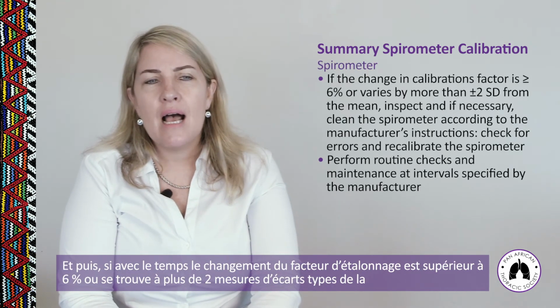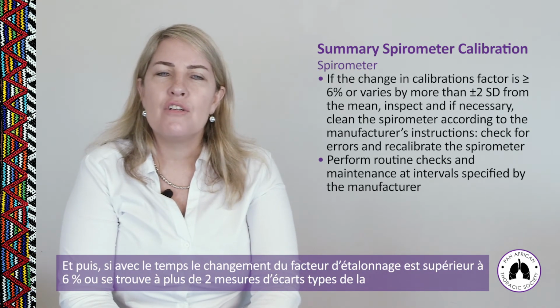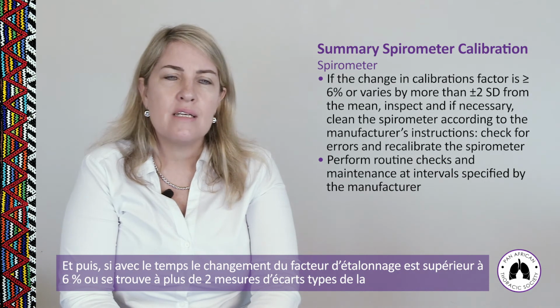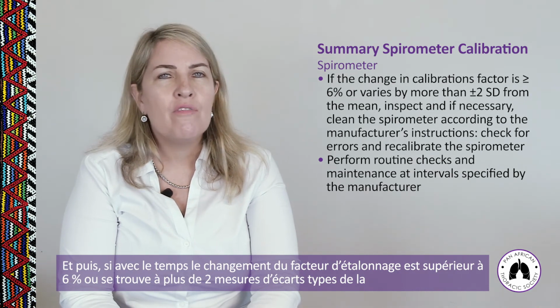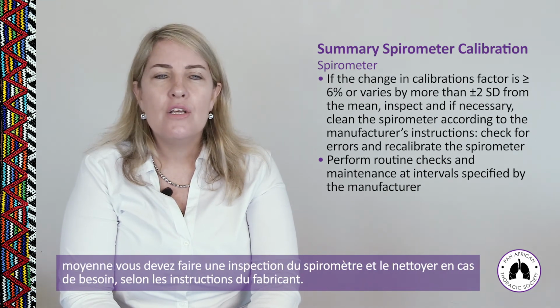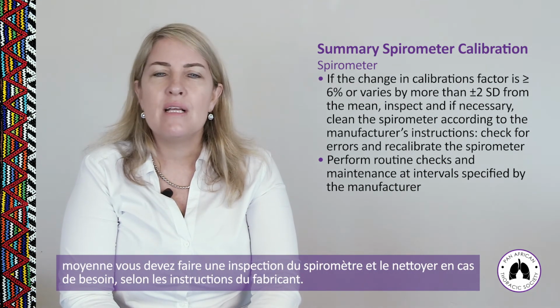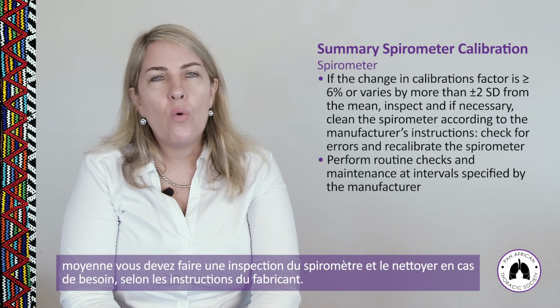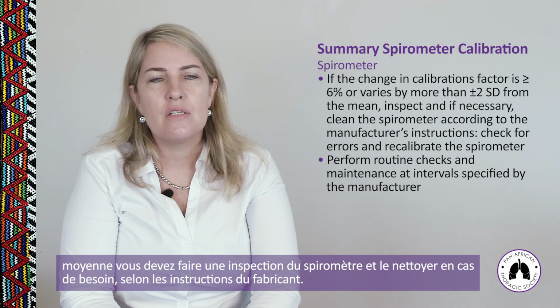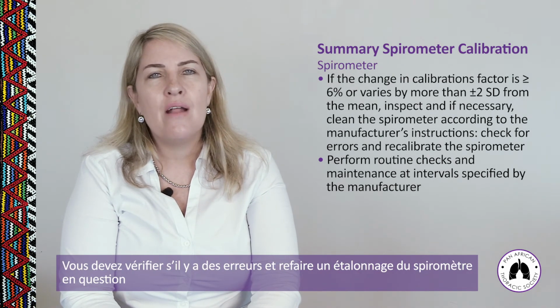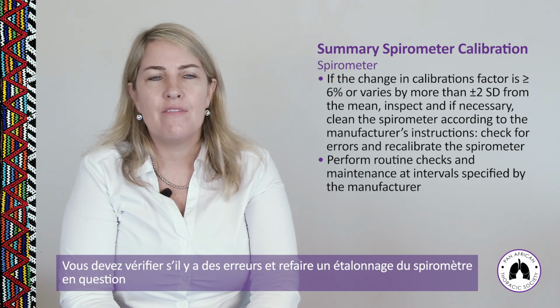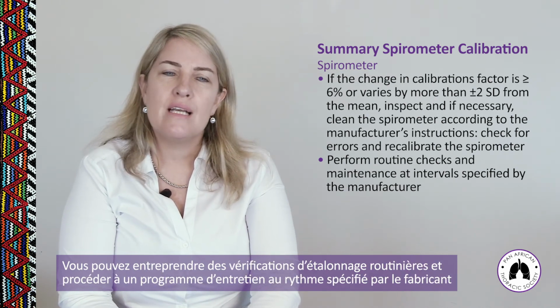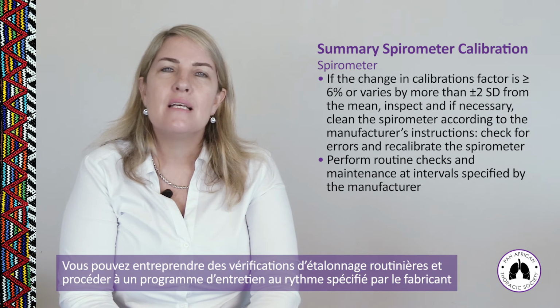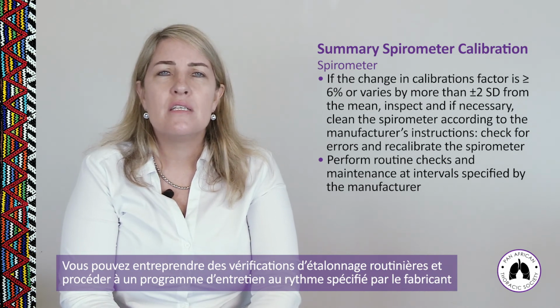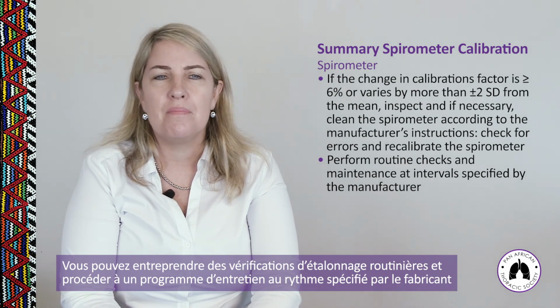And then in time, if the change in calibration factor is equal to or greater than 6% or varies by more than 2 standard deviations from the mean, you need to inspect and, if necessary, clean the spirometer according to the manufacturer's instructions. You need to check for errors and recalibrate the spirometer itself. You could perform routine calibration checks at maintenance at intervals specified by the manufacturer.